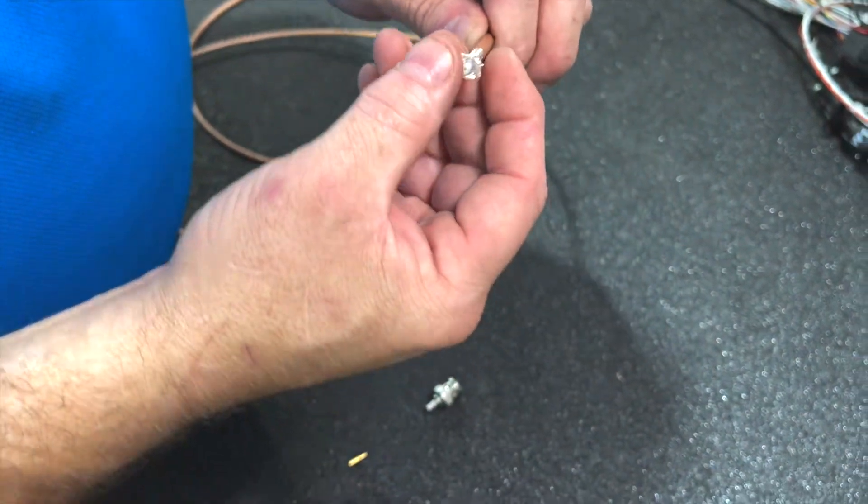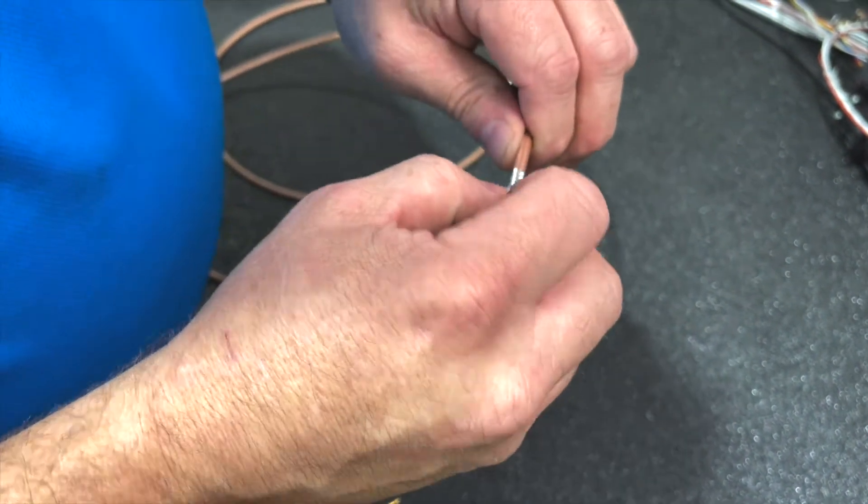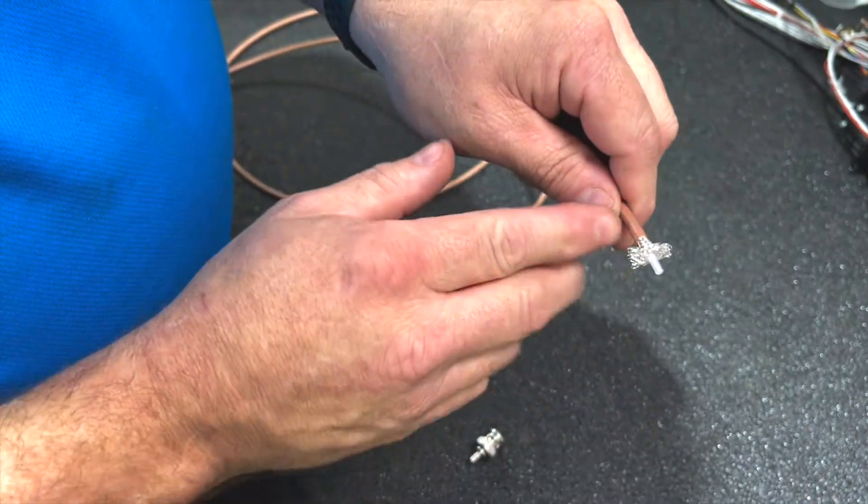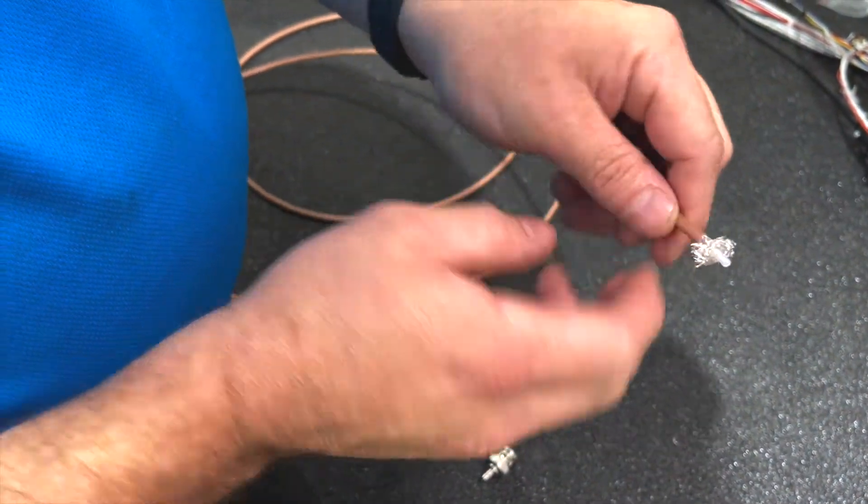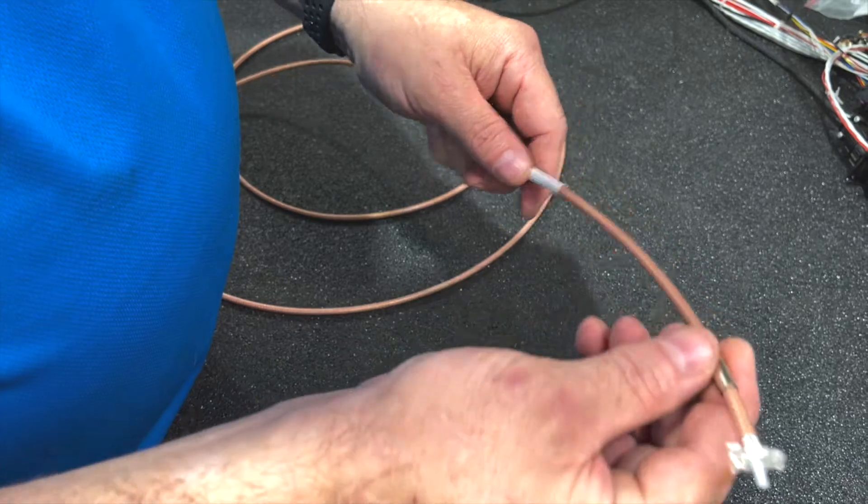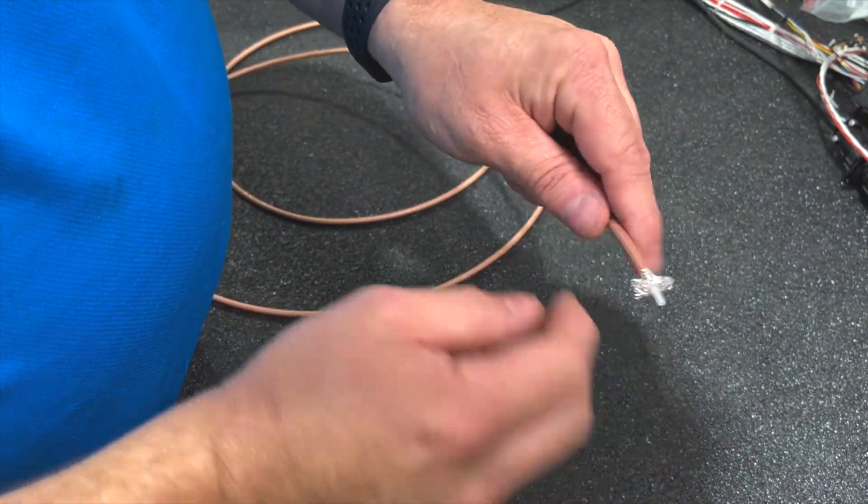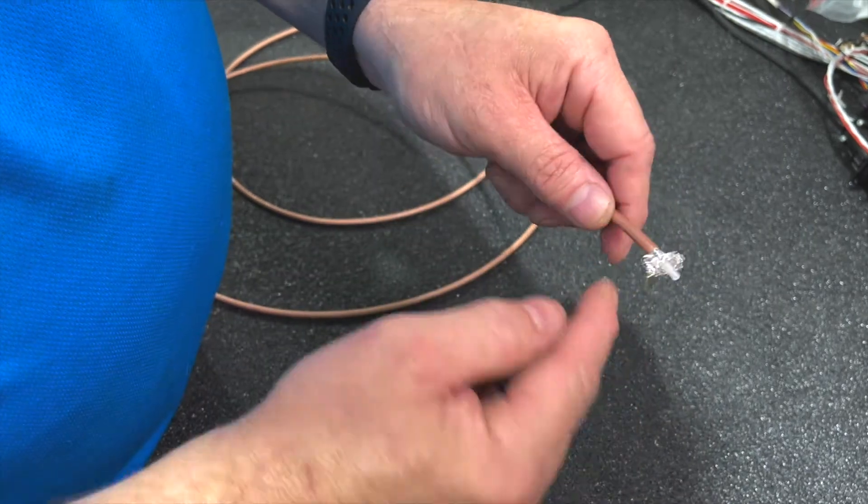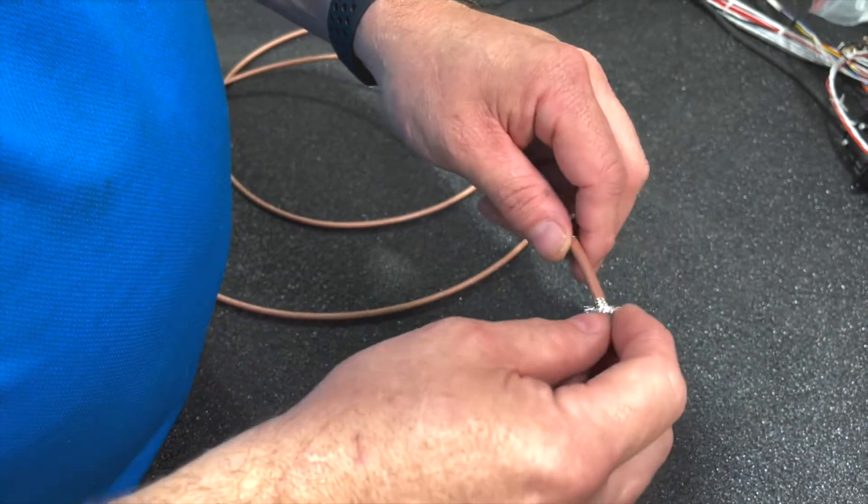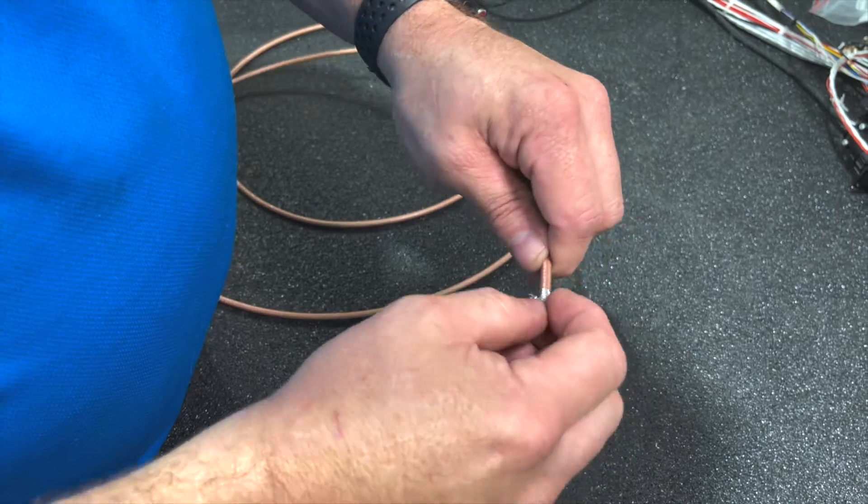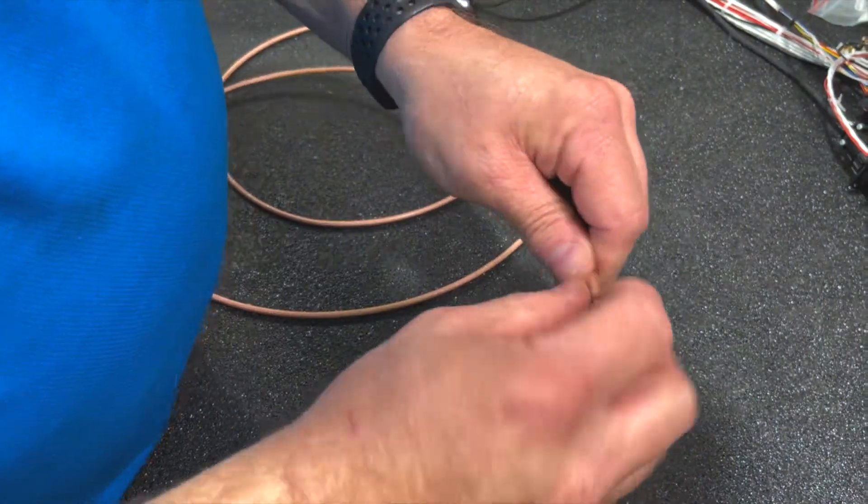Next thing we're going to do is push back the shielding. You don't want to cut this too far back, because then when we go to crimp on this sleeve, you'll have some shielding exposed and it makes for a weak joint. So we want to make sure we start about a half inch. If we have to take more off we can do that. You can't add it back on.